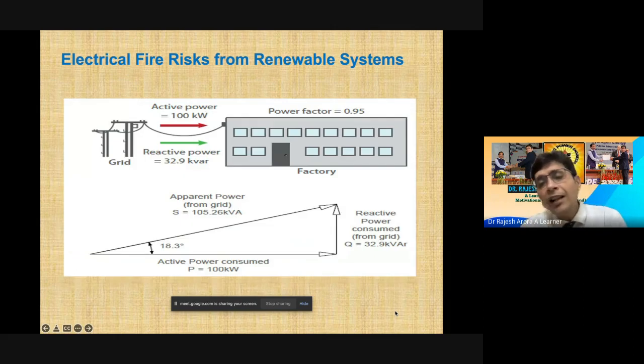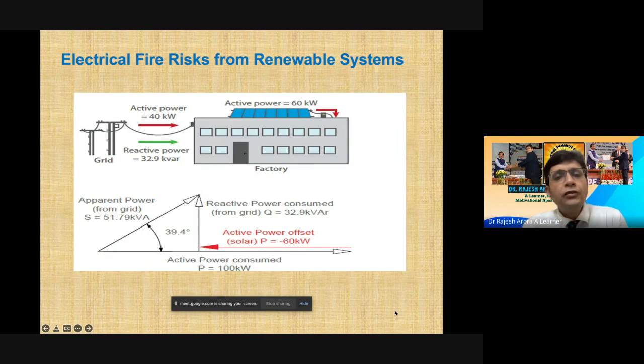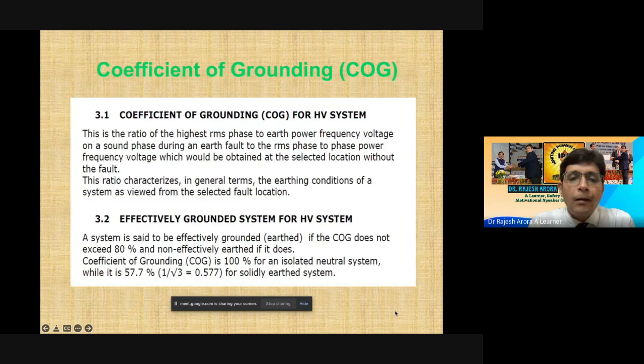This is a typical example I have taken. In that building, the power factor was 0.95 and all active energy was coming from distribution. Now, after installation of 60 kilowatt of solar PV on the top, the reactive power was still there, but active power reduced. Because of that, there is some change in the power factor, and we have to take care of that. Coefficient of grounding, COG, and effectively grounding system for HV system to be looked into.